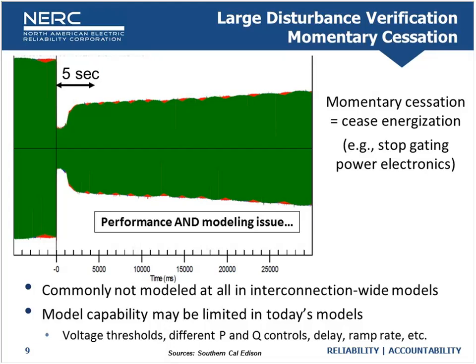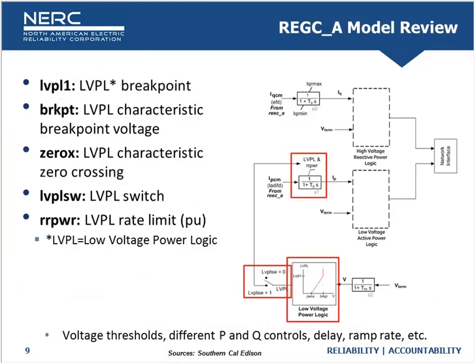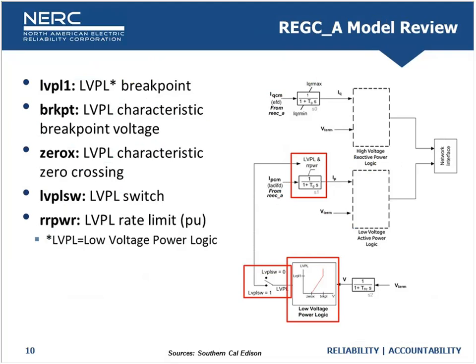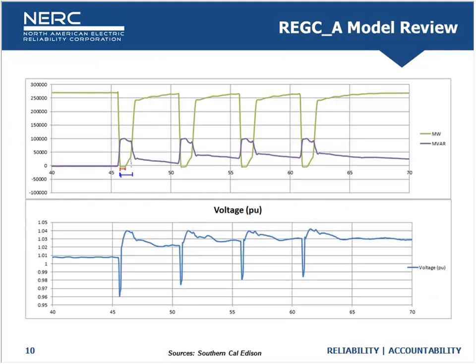We need to evolve in terms of standards, but also in terms of models and modeling practices. The tools need to have the capability, and the models need to be able to model momentary cessation fairly accurately. We're going to seek improvement on this in the next generation of models. The REGCA second-generation renewable model is what we're looking at for how to accurately model momentary cessation, and we'll have some guidance coming out to the industry on that shortly.